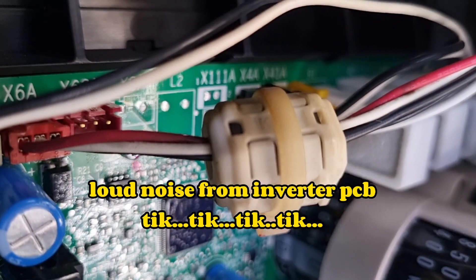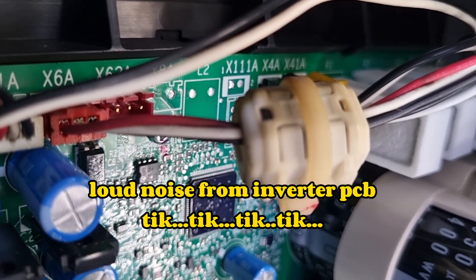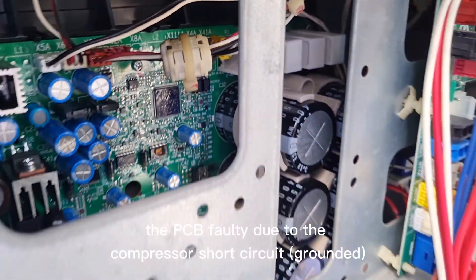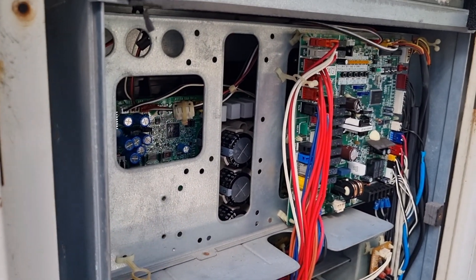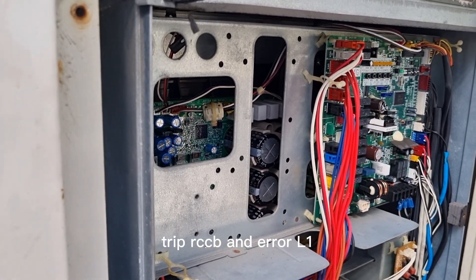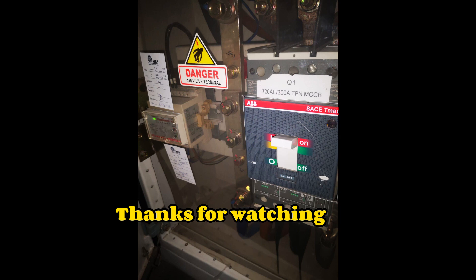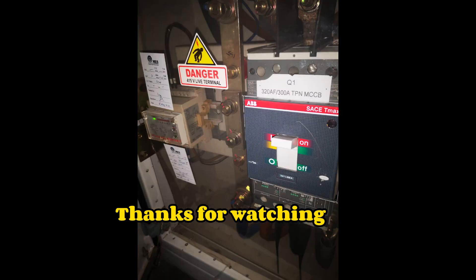The PCB burst area — you can hear the sound. The PCB became faulty due to the compressor being grounded, and the RCCB also tripped. Error L1. You can see — the PCB became faulty due to the compressor being grounded. Thank you.